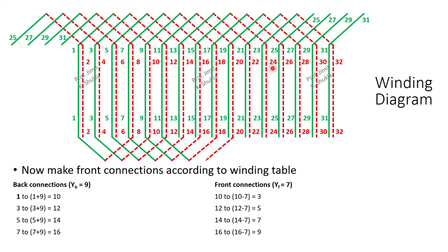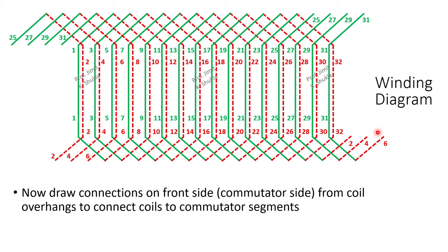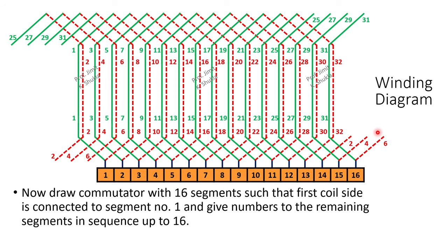We will make each and every connection as per the winding table. On the front side also, 27, 29 and 31 would be connected with 2, 4 and 6 to indicate the continuity of the winding. Now we will draw connections on the front side from coil overhangs to connect the coils to the commutator segments. Then we will draw the commutator with 16 segments such that the commutator segment connected with coil side 1 is given number 1, and so on.